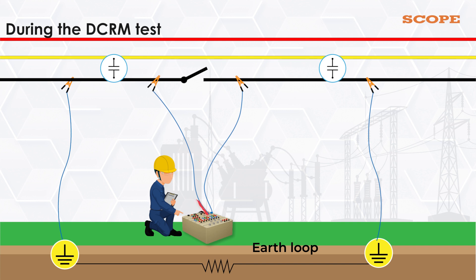During the DCRM test, depending on the resistance of the earth loop, a partial test current will pass through this loop. And for timings, this loop will show permanent closure of CB contacts irrespective of actual CB contact status.